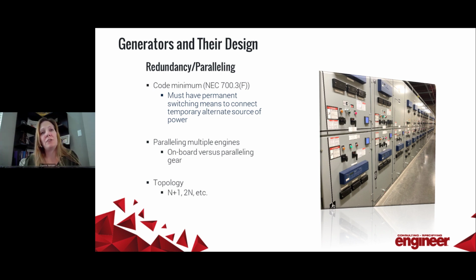So NEC Article 700.3 Part F states that if the emergency system relies on a single alternate source of power, which could be disabled for maintenance or repair, the emergency system shall include permanent switching means to connect a portable or temporary alternate source of power. So this would include any generator that supports your Article 700 systems, hospitals, high rises, and so on. However, this is simply code minimum. Many critical designs may warrant additional redundancies built into the system. There is a careful balance between figuring out the right redundancy and reliability. When you have the space, multiple engines provide more reliability than a single larger engine.